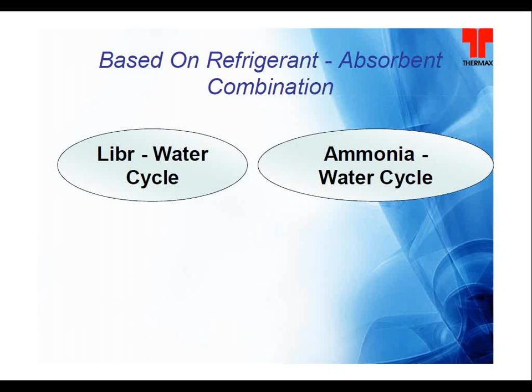Coming to the sugar industry, the application is majorly for the lithium bromide water cycle. This cycle can work up to -2 degree brine on the chilled water side. In the sugar industry, -2 will not be an application, but something like 7 degree, 10 degree, which is an air conditioning load or the process load, can be given through this vapor absorption machine through the lithium bromide water cycle. This is the entire working.